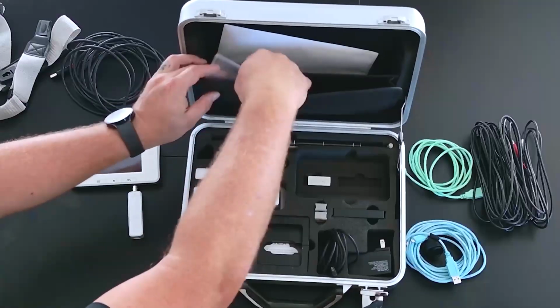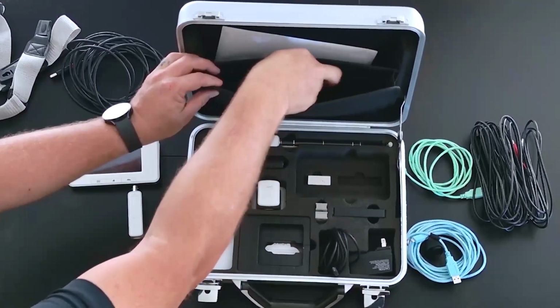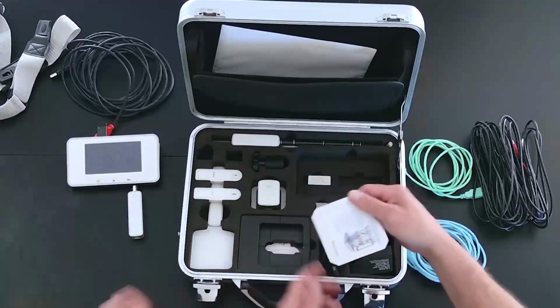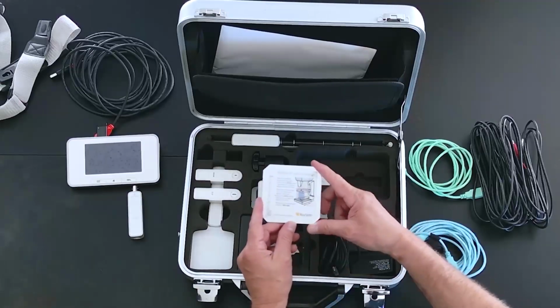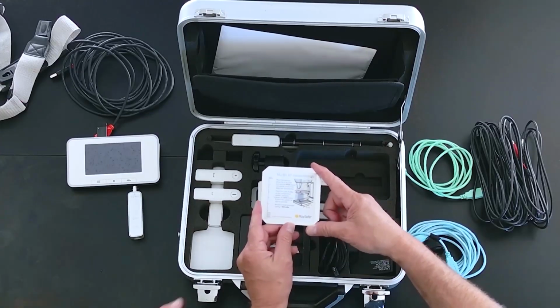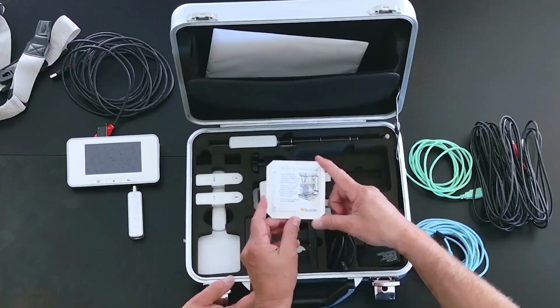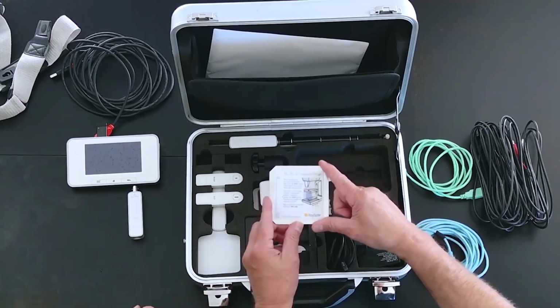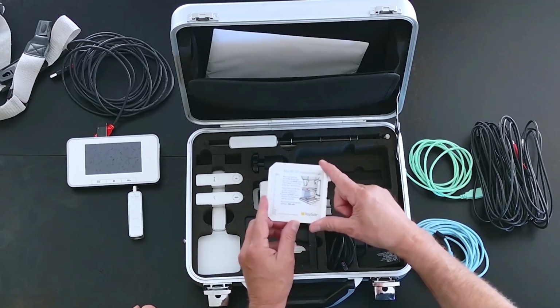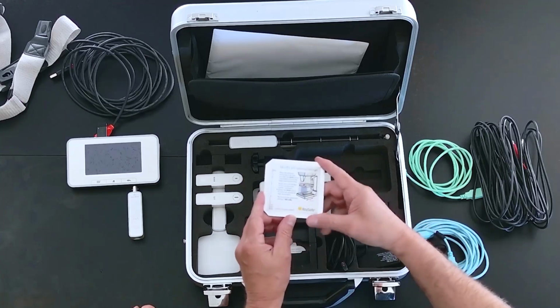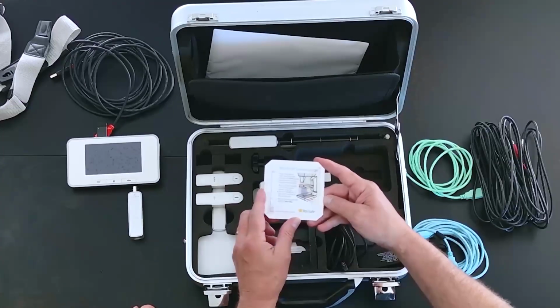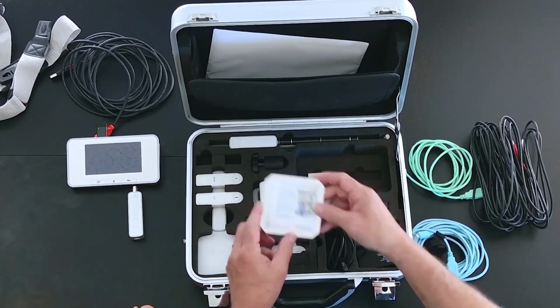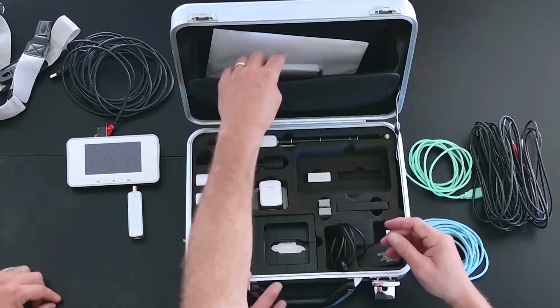Oh yeah, there's a piece of aluminum. So if you have the MAM sensor, you're going to get this 2 millimeter piece of aluminum, and this is used when we measure kV specifically on the Moly target rhodium filter. So for Moly rhodium kV measurements, you use this and you set it on the compression panel. Cool. I'll throw that back in. Yep. Otherwise we'll lose it.